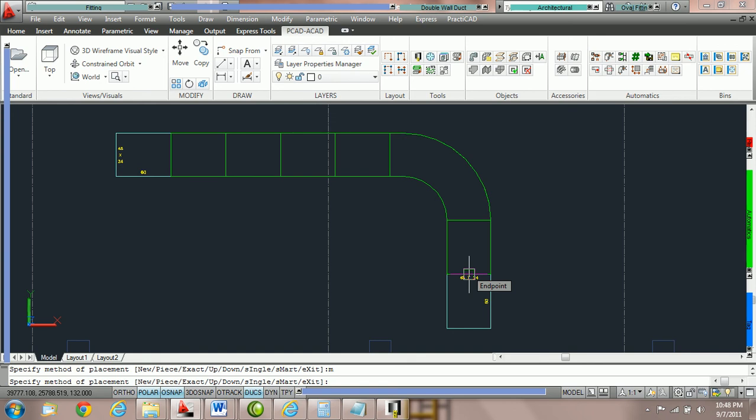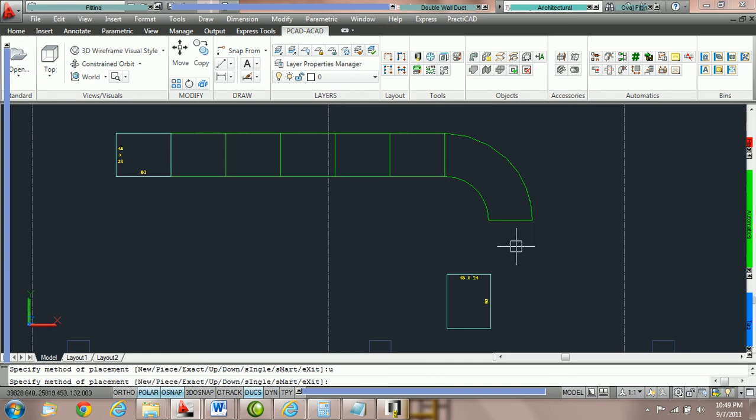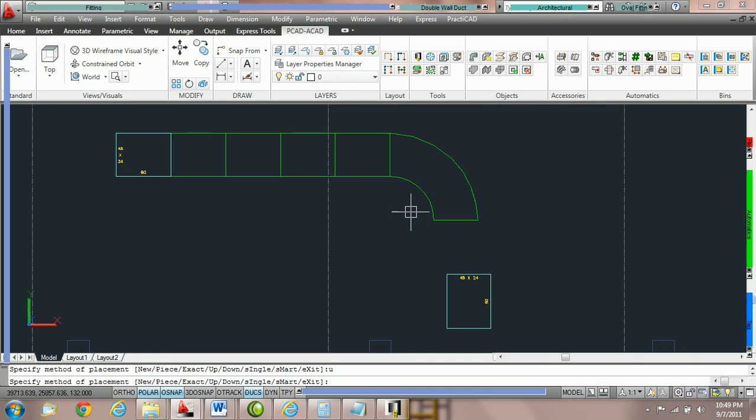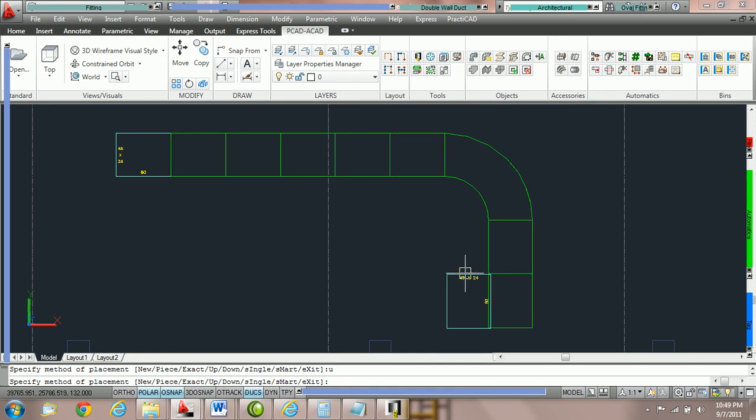The other two methods are up and down. They're very similar. Most of the time I will just use up. All you need to do is click on U for up and hit spacebar and now move your mouse left to right and you'll notice that you're routing in up which is always full joints. So you will not be able to connect these two pieces of duct unless you switch the routing method back to exact. Do that now by hitting E and the space or enter bar.